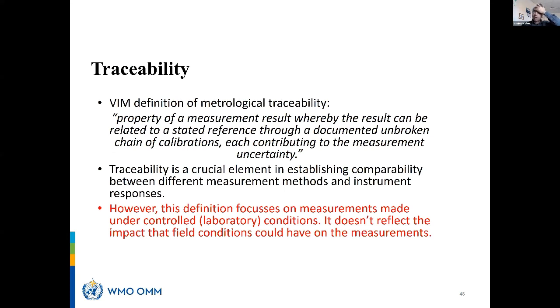Take care, there is a debate about traceability, because traceability is fit for the laboratory. It says that it's a property of the measurement result to be linked through an unbroken chain of calibrations, each one contributing to the uncertainty. But it doesn't speak about the environmental conditions. So please, it is not enough that your instrument is calibrated and you deploy it in the field. It is not enough to get traceability. You also have to detect the environmental effects.